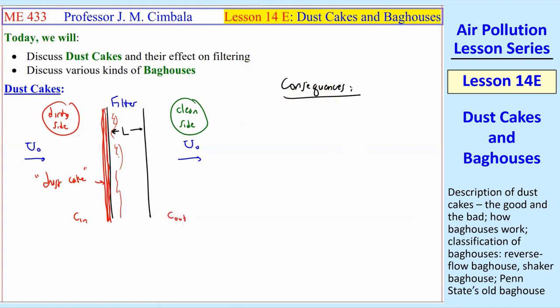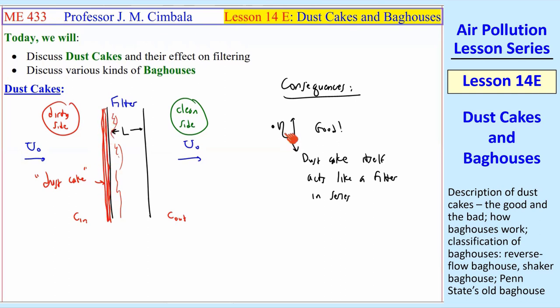What are the consequences of this dust cake that builds up? Well, the efficiency goes up, so that's good. What happens is the dust cake itself acts like another filter in series with the real filter. So this dust cake is actually collecting particles by itself like a filter, making eta go up. That's a great thing, so why don't we just let the dust cake keep building up?